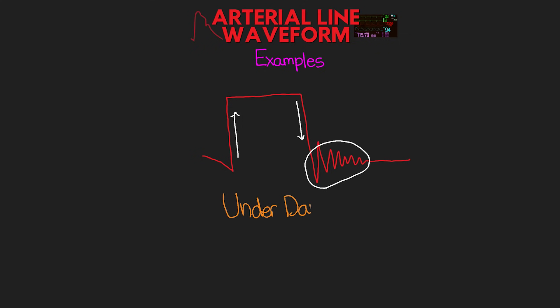Let's look at another example of a square wave test. If you saw this result, what would this be? Hopefully you saw that quick upstroke and quick downstroke, but you saw an exaggerated number of oscillations at the end — this would be an indication of underdamped. Knowing this information, what would you expect to see with your patient's arterial blood pressure tracing? This should tell you that you would see too much energy in the system, thus an exaggerated waveform, giving us that higher systolic and lower diastolic blood pressure.